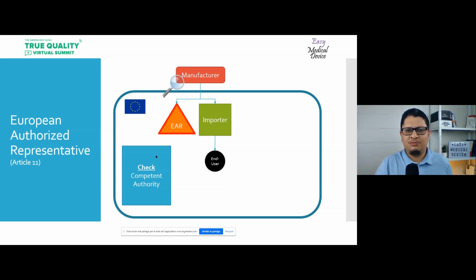There is no label saying "distributed by," even if maybe you can put that, but there are no legal requirements to do that. The only thing that he has to do is also to verify that the importer label is there, if it's a product that is imported. Verify again that the UDI is there. Verify again that the EU declaration of conformity is there. You see that at many stages we are verifying the same kind of things. And he has also to do a sampling method to verify this on the product. So if you have a pallet of 500 products, you have to define a sampling method of collecting maybe 10 products from here, 10 products from there, etc. So he has to define this method and use that for inspecting that the product is correct. And then he can deliver the product.